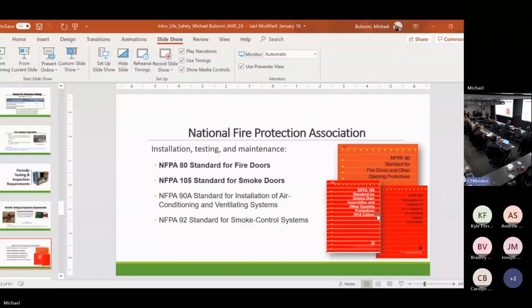Then 1 year later, I test the damper again. And then in commercial buildings, every 4 years, I test my damper. In hospitals, it's every 6 years. And we do this for 2 reasons. One, we commission it, test it a year later, and then 4 years later, so the damper has been tested 3 times in a period of 5 to 6 years. In the first 5 years of a new building, how many times do you go into a building and new walls are put up, new offices are made?